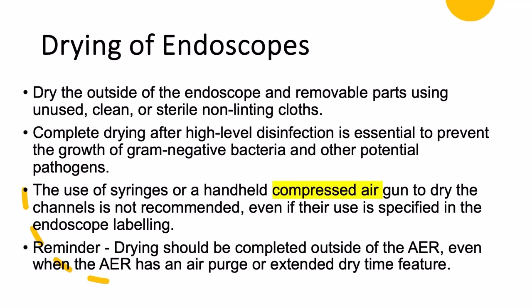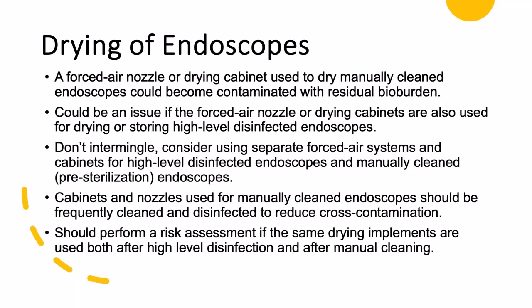The use of syringes or handheld compressed air guns to dry the channels is not recommended, even if their use is specified in the endoscope IFU. Remember, drying should be completed outside of the AER, even when the AER has a purge cycle or extended dry feature. A forced air nozzle or drying cabinet that's used to dry manually cleaned endoscopes could become contaminated with residual bioburden. This could be an issue if the forced air nozzle or drying cabinets are also used for drying or storing high-level disinfected endoscopes, so don't intermingle them.